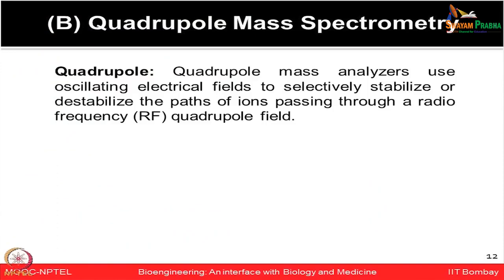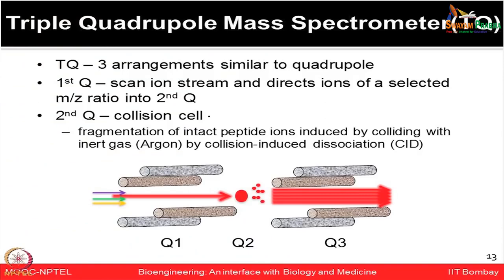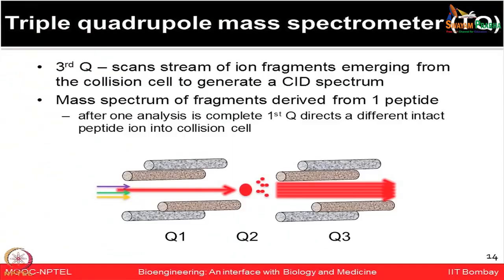Quadrupole-based mass analyzers use oscillating electric fields to selectively stabilize or destabilize the path of ions passing through a radio frequency quadrupole field. In a triple quadrupole configuration, the first quadrupole scans the ion stream and directs ions of a selected mass-to-charge ratio; those selected ions are fragmented in a collision cell using collision-induced dissociation with inert gases like argon; then the third quadrupole scans the resulting ion fragments, generating a CID spectrum.